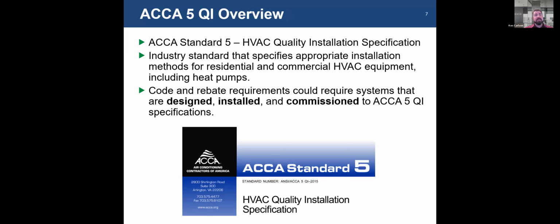ACCA 5 is the HVAC quality installation specification. If anybody's not sure, doesn't know what ACCA is, Air Conditioning Contractors of America. They set out different standards in the air conditioning realm, including manual J's, manual S's, manual D's, all of which can be found through the ACCA. So ACCA standard 5 has to do with quality installation. It's basically a quality installation specification. It's the industry standard that specifies appropriate installation methods for residential and commercial HVAC equipment. Heat pumps are included in that specification.